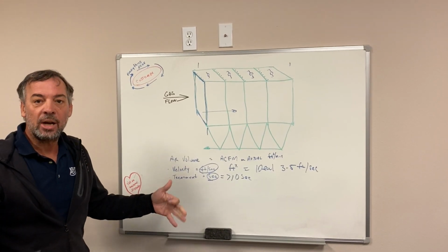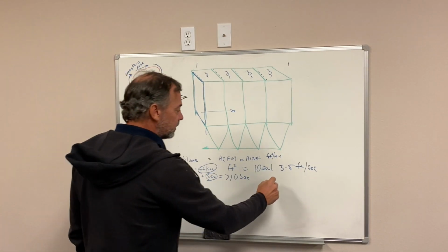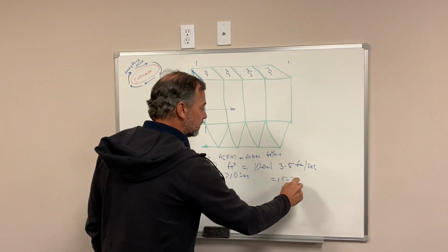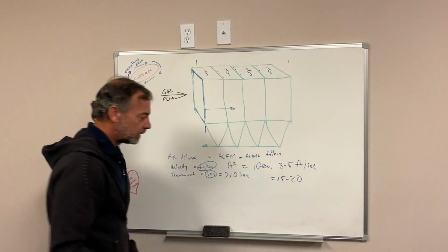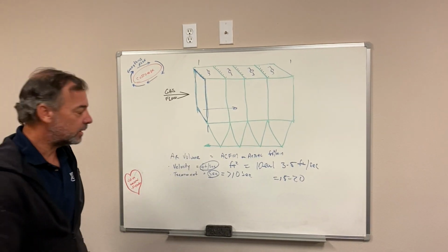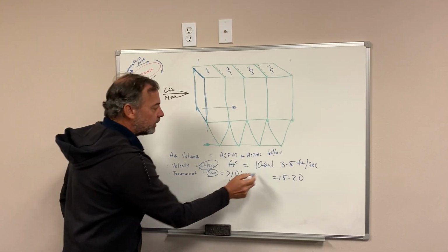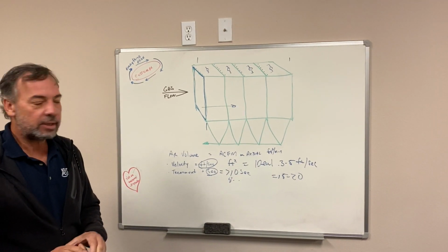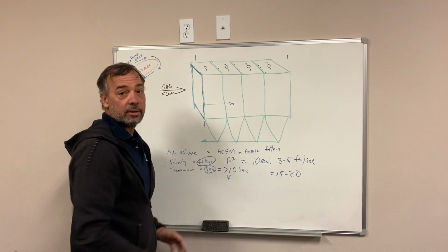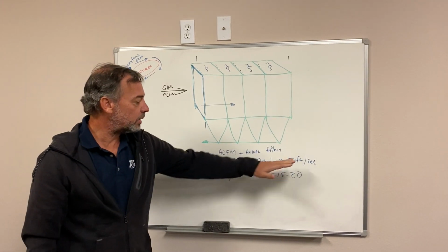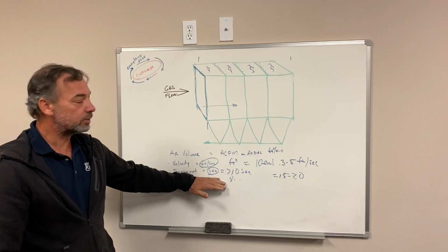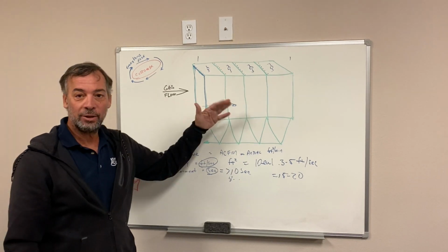Sometimes in severe high resistivity cases, you get up to 15 to 20 seconds of treatment time. Recovery boiler precipitators, things of that sort, you're in the 8 to 10 seconds. But once you have these two numbers, you can quickly see, is my precipitator physically big enough? If you have way too much velocity or way too little treatment time, there's not much we can do for you.